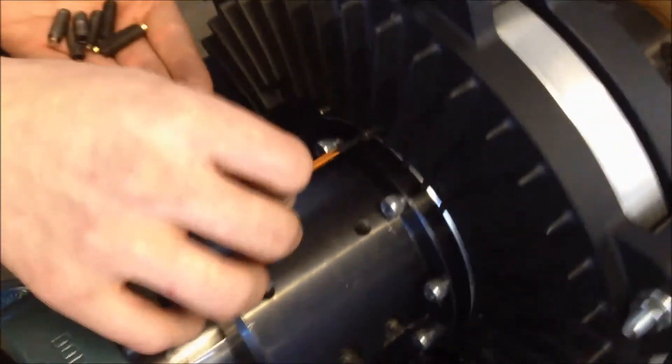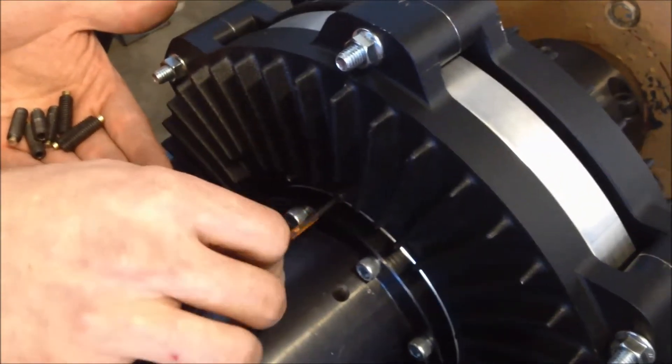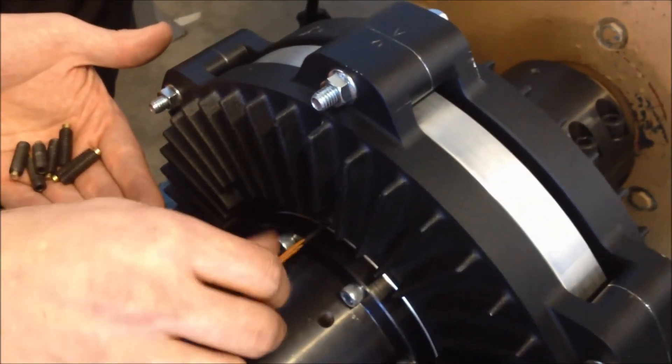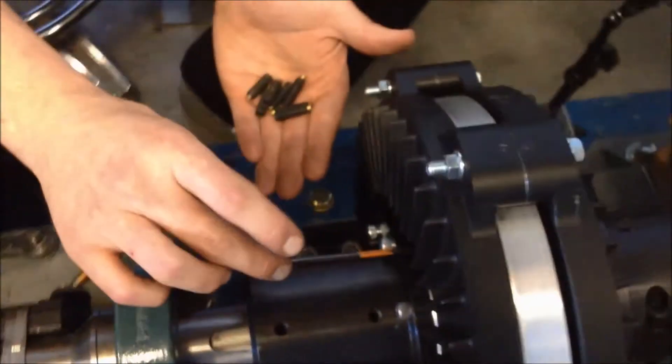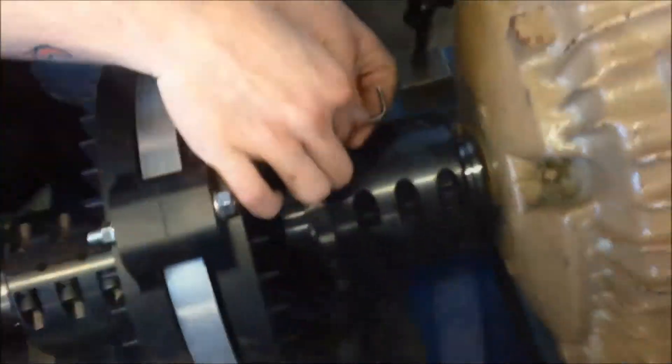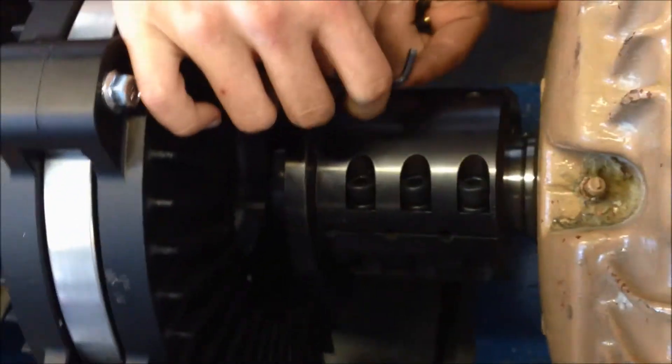Insert the four supplied jacking bolts into the threaded holes on the induction rotor face. Screw them in until they just come into contact with the magnet rotor. Follow the same procedure on the other side.